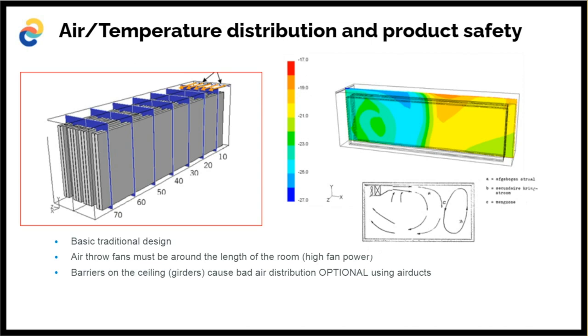And maybe it's not such a big deal, but you just go deeper in evaporation temperature and use extra energy to get all the temperatures within the range. But it's not the perfect solution. So the airflow of the fans has to be so much that it has to reach the other side of the room, preferably. So that's a lot of power. And there are barriers and all kinds of other stuff, causing a not very nice flow of the air.